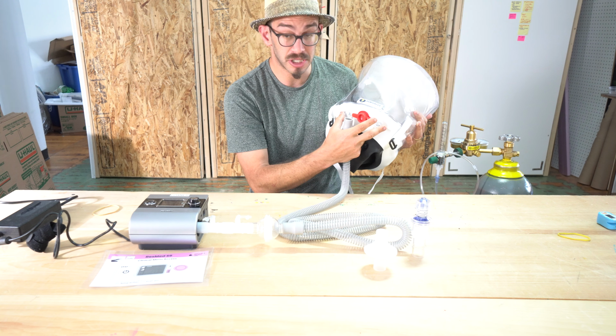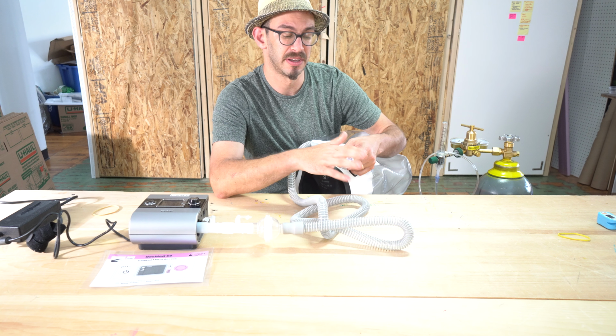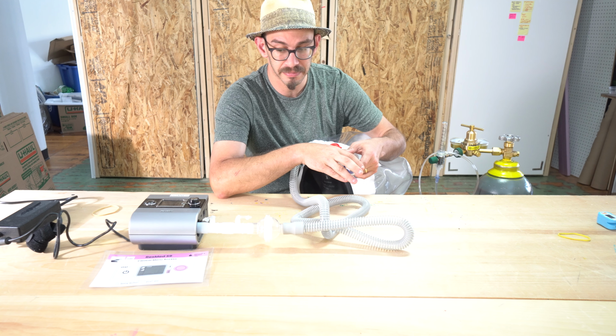On the other side, we're going to place the expiratory filter and a PEEP valve. The PEEP valve is adjustable, and I'd like you to open it all the way up. So the minimum PEEP is 5 centimeters of water pressure, and I'd like you to set it to that and keep it there, not adjust the pressure here.